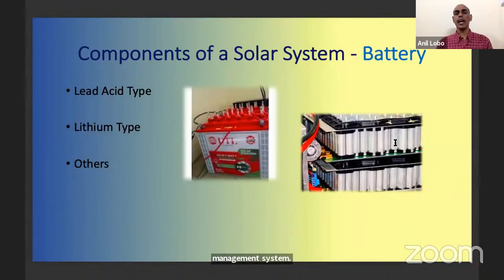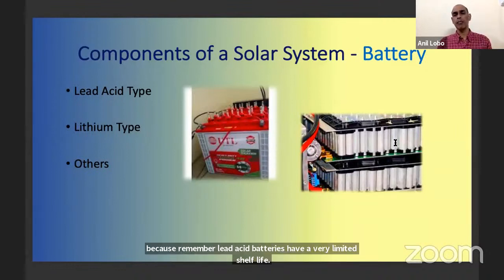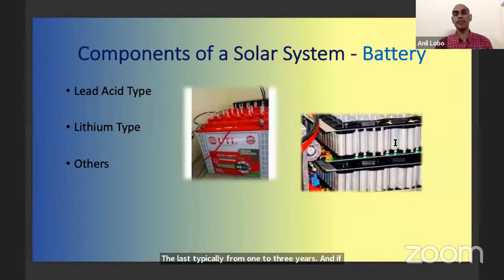If you're going for something which will last longer, because remember, lead acid batteries have a very limited shelf life. They last typically from 1 to 3 years, and if properly designed, there are some batteries today that can last up to 5 years. So if you're going for a lead acid battery that will last for 5 years, make sure that you have a good battery management system so that you can charge and discharge it at an optimum level. Lithium batteries require a very sophisticated cooling system. So you cannot just put a couple of lithium batteries together and say, voila, I have a lithium battery bank. Lithium batteries need to be cooled, and there are various methods. The most efficient cooling system is using a liquid cooling system, where the liquid is circulated and you have some sort of a way of venting out the heat through some louvers or fans.